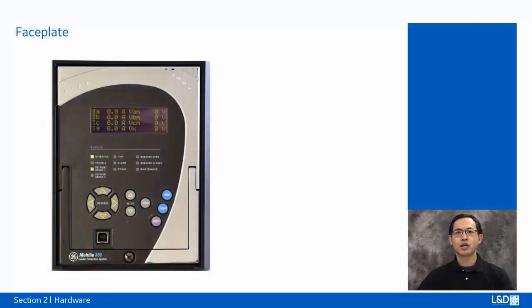On the front panel, there is a 4x20 character LCD display screen that allows visibility under varied lighting conditions. When the keypad and display are not being used, system information is displayed after a user-defined period of inactivity. Any trip, alarm, or pickup is displayed immediately, automatically overriding the default message. If the keypad is inactive for the preset screensaver time, the relay automatically shuts off the display screen. Below the display screen are the status indicators, with 10 LEDs for the non-programmable type and 12 LEDs for the programmable type. These LEDs show the status of the relay operation and the breaker, or for the motors or transformers, depending on the application of the relay.